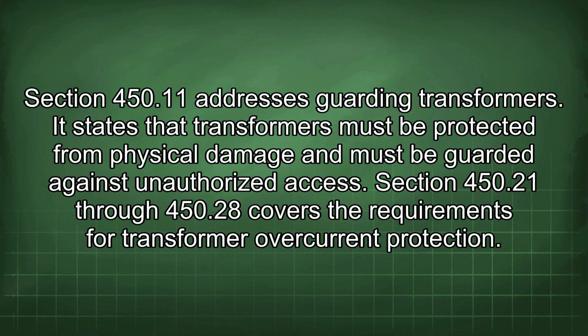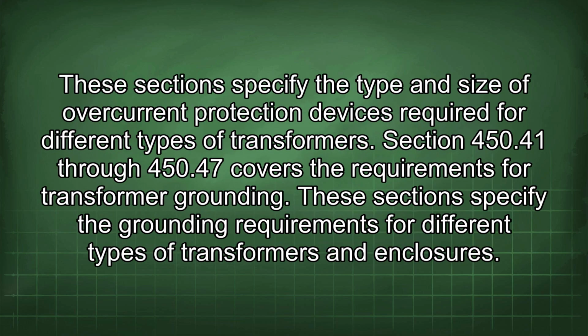It states that transformers must be protected from physical damage and must be guarded against unauthorized access. Section 450.21 through 450.28 covers the requirements for transformer overcurrent protection. These sections specify the type and size of overcurrent protection devices required for different types of transformers.